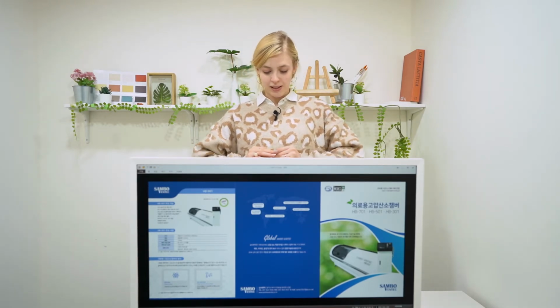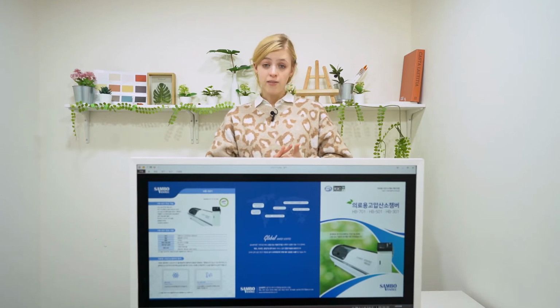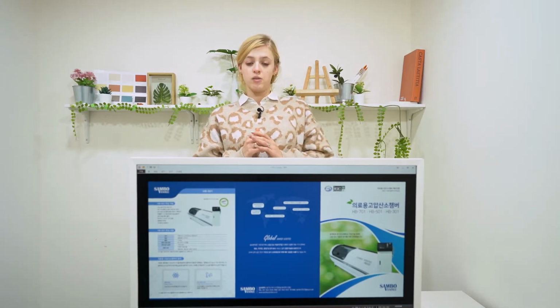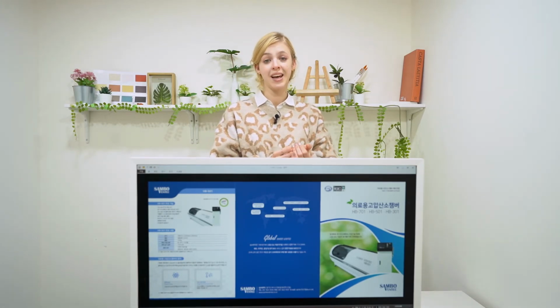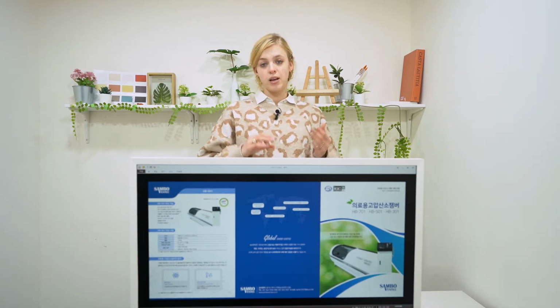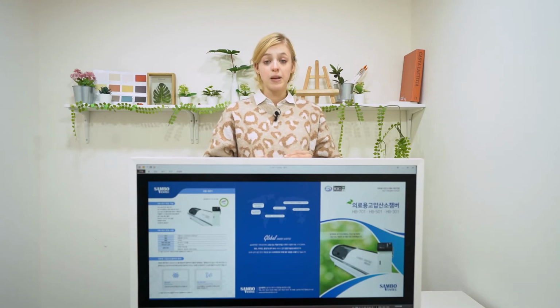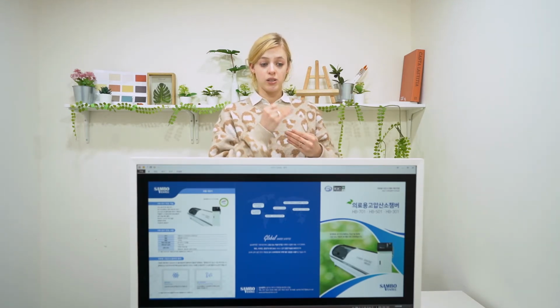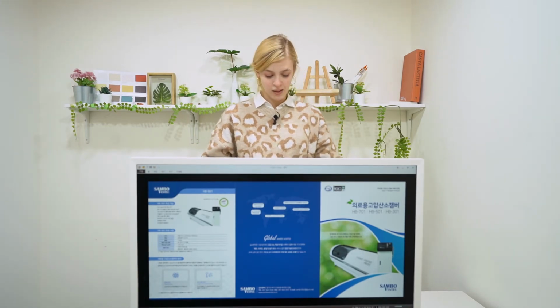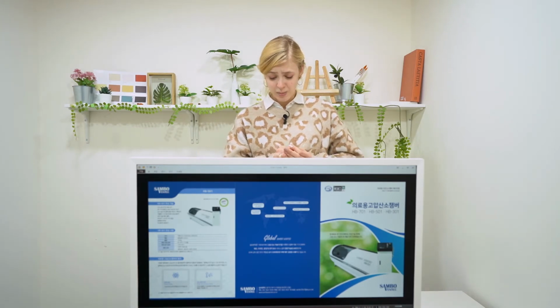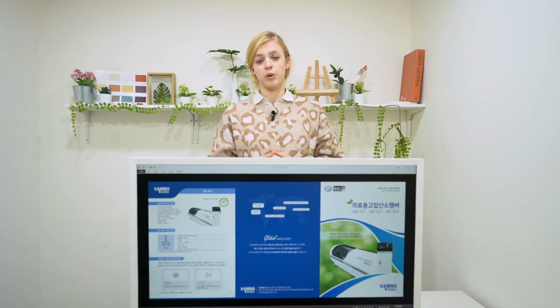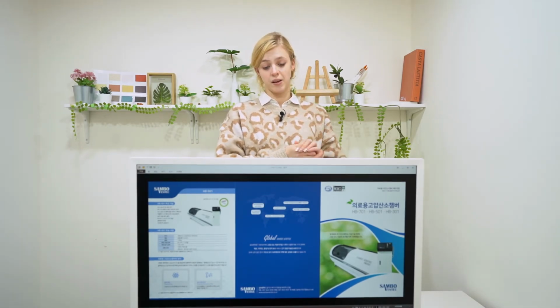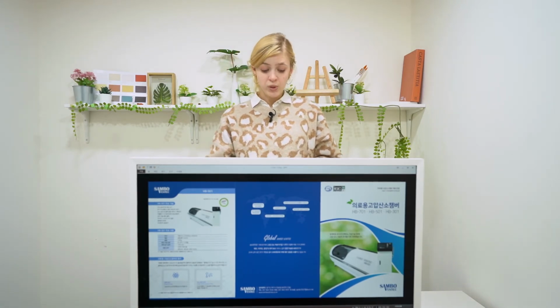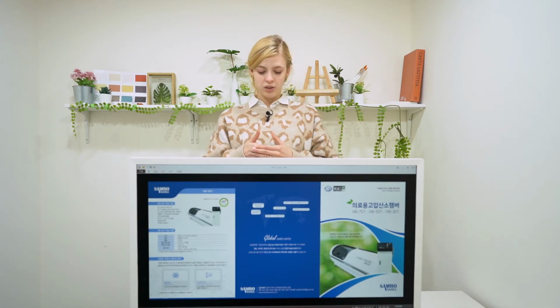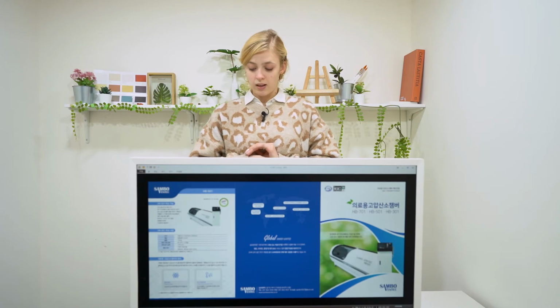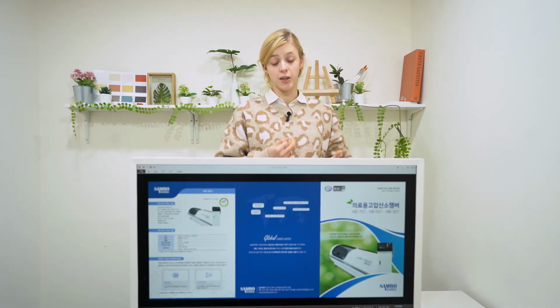The blocking software pressure automatically stops when the pressure inside of the chamber exceeds 35 kPa. It is also a safety measure. There is no way you could get hurt by the machine. It only is trying to make you better. It's only aimed at doing all the good things, and even if a malfunction is going to happen, it automatically shuts down. It's going to automatically shut down everything that is going to go wrong in the process. Compressor safety side pressure compressor blocks excess pressure of 80 kPa or more. So it is very safe even in the compressor point of it. The recording device stores time and oxygen concentration every 1 minute for 3 hours. In the event of a safety accident, it's possible to check whether the device is operated normally.